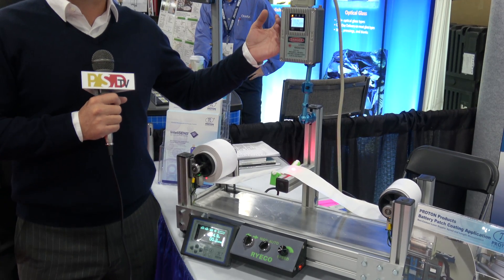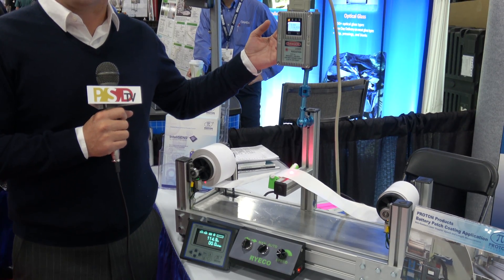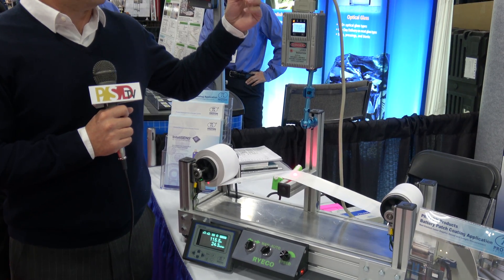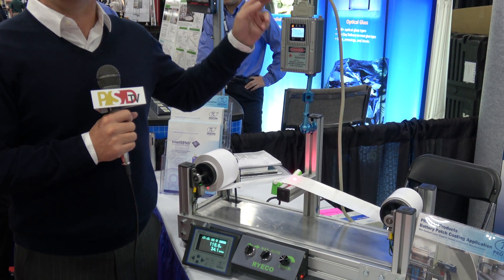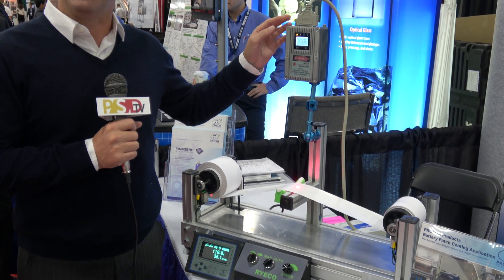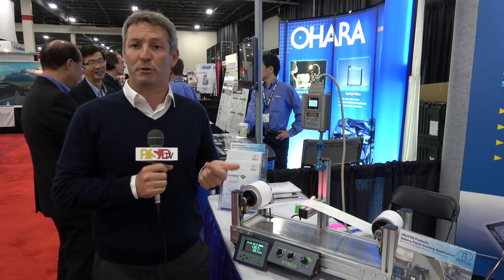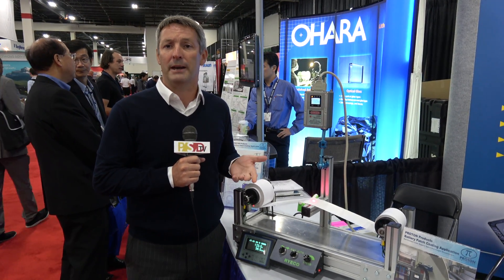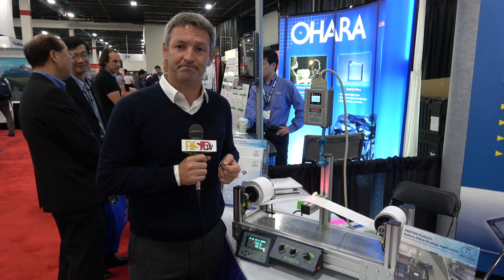These devices are accurate to better than 0.05%. They have pulse outputs, relay outputs, digital inputs, Ethernet, TCP/IP, and they can also be fitted with either Profibus, Profinet, DeviceNet, or EtherNet/IP for connecting to PLCs. Thank you.